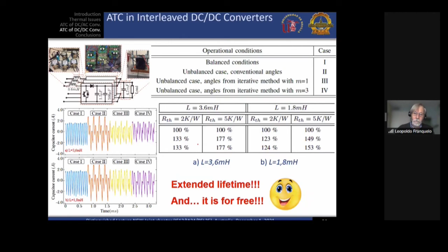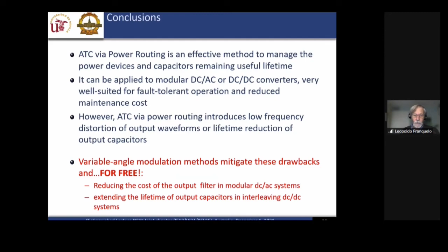As conclusions, we have been using active thermal control via power routing. We show that it's an effective method to manage the power devices and capacitor remaining useful lifetime. It has been applied to modular inverters and DC-DC converters, and is very well suited for fault-tolerant operation and reducing maintenance costs. But of course, it has some drawbacks, creating low-frequency distortion. Fortunately, with techniques of controlling the angles of the modulation method, we mitigate this drawback for free. So we can reduce the cost of the output filter in modular DC to AC systems, extending the lifetime of our capacitors in interleaving DC-DC converter systems.